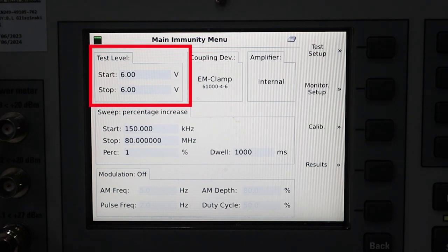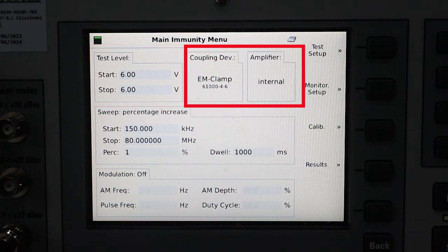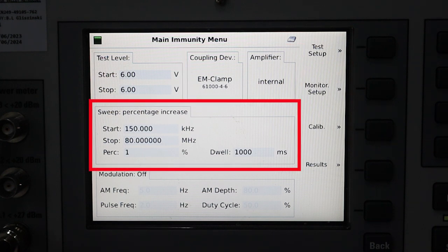You can see we have a couple different boxes here. We have a test level currently at six volts. We have our coupling device which is an EM clamp in accordance with IEC 61000-4-6. We have an internal amplifier selected, and then we have our sweep from 150 kilohertz to 80 megahertz. So everything looks good there.